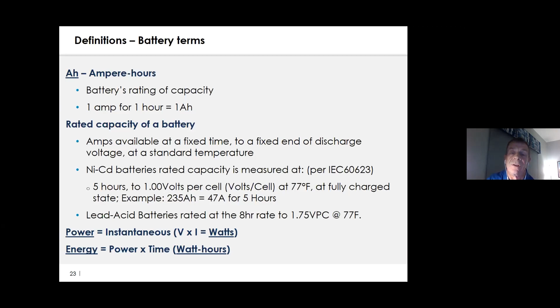Now, just to go over some of the details about the batteries we have: you've got amp hours, defined as 1 amp of current for 1 hour, which becomes the amp hours. Typically we're using 9 or 12 amp hour batteries, particularly at the VRLA level. The temperature rating is very important for the batteries, because the hotter they are, the less amp hours they drain off their stored power, which becomes problematic when they're needed.